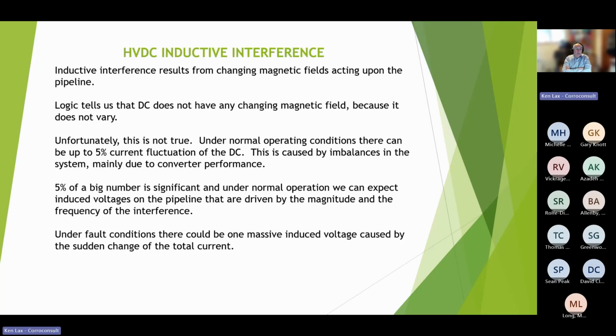So having explained to you that DC doesn't vary, you can logically assume that it will have a magnetic field, but it doesn't change. And because it doesn't change, you won't get any voltage induced in it. Unfortunately, this isn't the case with high voltage DC, because as you'll see a little bit later on, we have to do various things to this DC to prepare it and then squeeze it down the line. And part of that results in about a 5% current fluctuation of the DC.